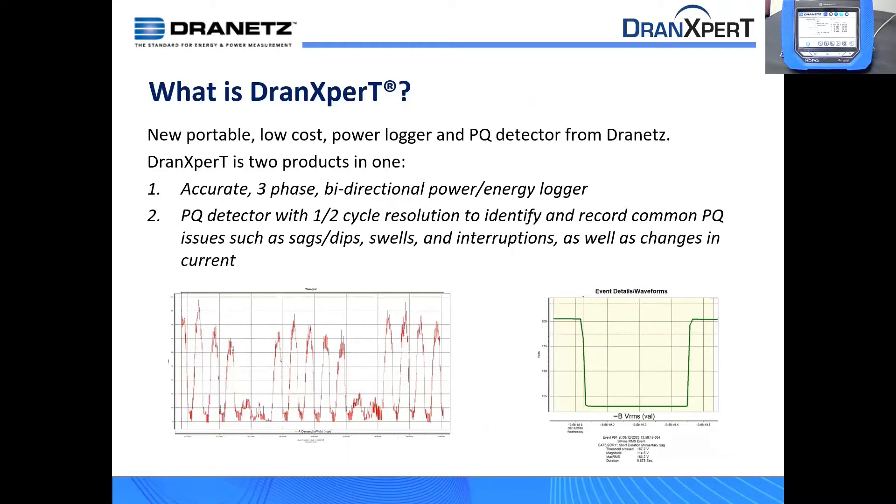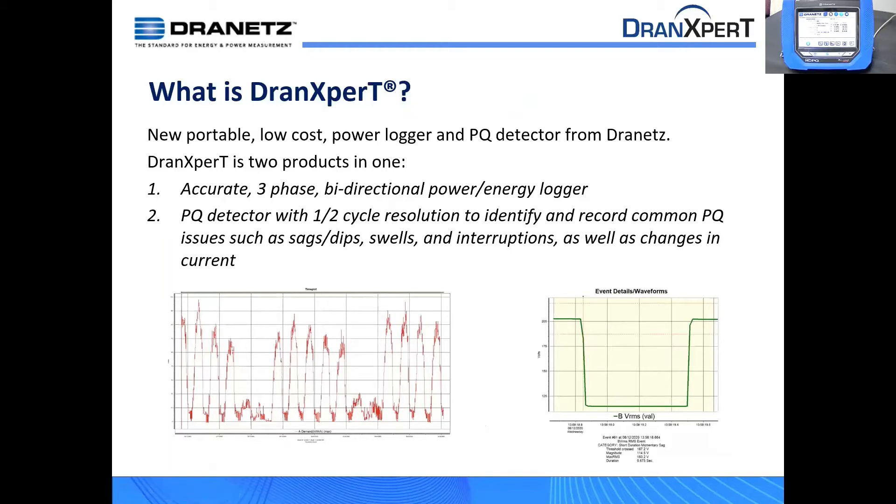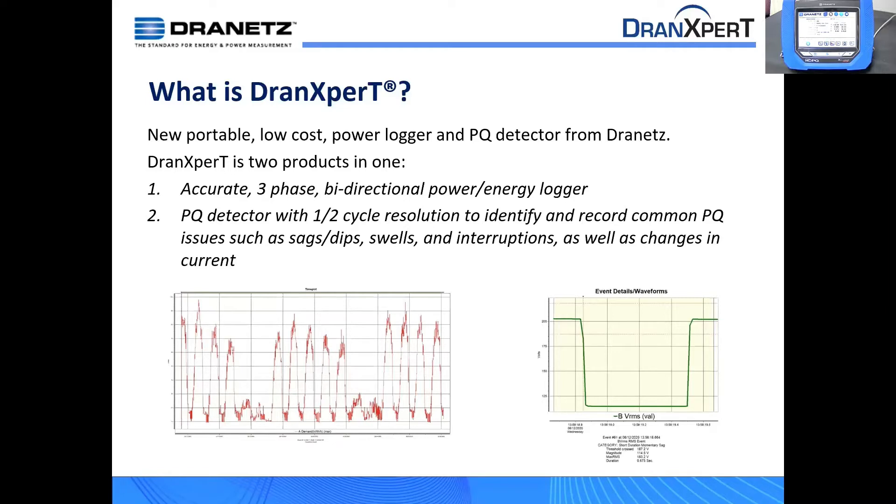So it's really two instruments in one. It's an accurate three-phase bi-directional power and energy logger, but it also has parallel power quality detection capabilities. As you can see on the right, this is a dip that occurred. It can record the wave shape, the RMS shape of a dip or a swell. It does not have transient capabilities. It has no wave shape capabilities when it comes to power quality. So these capabilities are not to replace our higher-end instruments, our HDPQ products or others, but it does give you basic PQ detection capabilities. So if you see PQ issues, then you can go get one of our higher-end products to actually troubleshoot and diagnose these products.